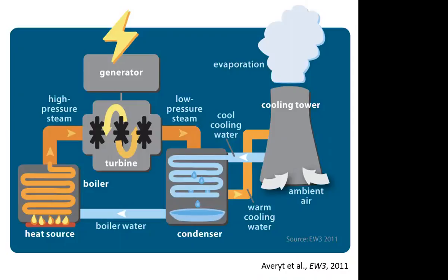The important part of this cycle is ensuring that when you create the steam, it recondenses, so the cycle can continue and you can keep generating electricity. The reason power plants need so much water is because the most efficient way to recondense the steam is to bring a lot of cold water through the plant, so that cold water absorbs the heat. This cooling water accounts for over 95% of all water used in a power plant. So from extraction all the way to electricity generation, cooling water makes up the bulk of all water used by the energy sector across the US.